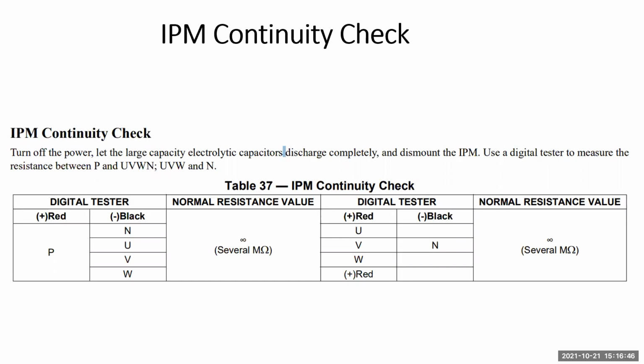So you're going to look for a P or the N terminal on the capacitor. Now we're going to be checking for resistance. There's no real set resistance. We're just looking for close resistance. You want the same amount. So you're going to check between P and UVW. You want to make certain you got a good connection from your meter. All these IPM boards have a positive and negative side, and it just depends where your meter leads land. It's much more accurate if you're on the positive side than what it is on the negative side.